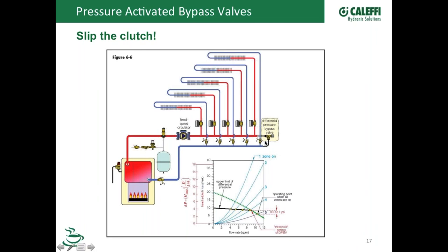So that's what this valve is doing essentially in this drawing down here, is we're just flattening that curve out, trying to make that curve of that pump that was up here and turn it into a flat curve pump, so that the head that we're adding to that circuit, as the flow rate changes, as the valves close, stays fairly flat, fairly consistent. So that's another way around a job that's got a fixed speed pump that you have zone valves on, is just put a bypass valve in it.